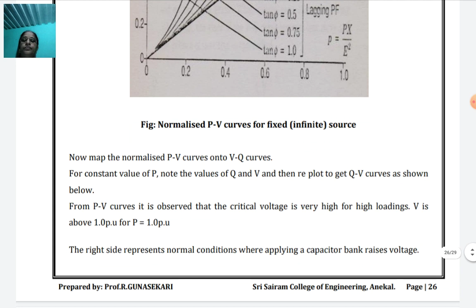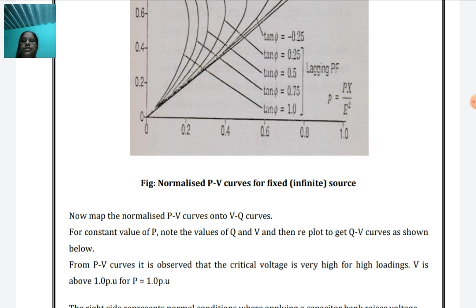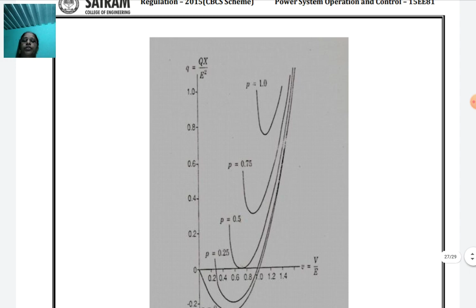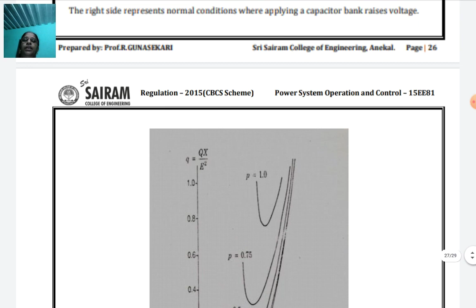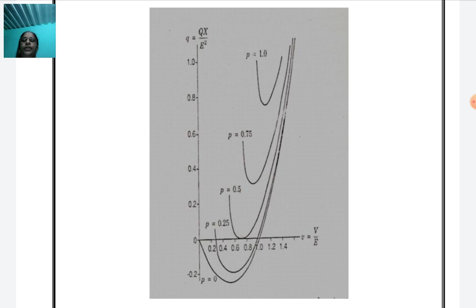From the curve, for a constant value of P, the real power, and the reactive power and voltage, we have to replot the QV curve. This curve is the PV curve, real power versus voltage. Why do we have to replot? For a constant value of real power P, with the values of power Q and voltage V, we replot the QV curve. In the QV curve, the y-axis is Q and the x-axis is V. We draw the curve, which is U-shaped, for different real power values from 0 to a maximum of 1.